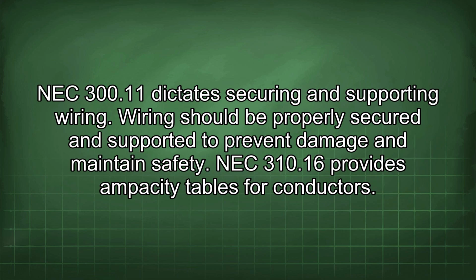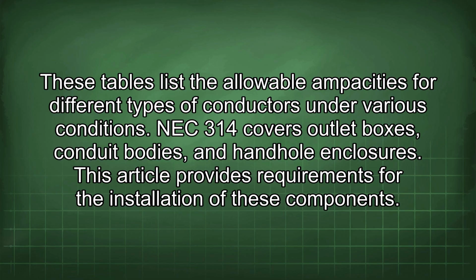NEC 300.11 dictates securing and supporting wiring. Wiring should be properly secured and supported to prevent damage and maintain safety. NEC 310.16 provides ampacity tables for conductors. These tables list the allowable ampacities for different types of conductors under various conditions. NEC 314 covers outlet boxes, conduit bodies, and handhole enclosures. This article provides requirements for the installation of these components.